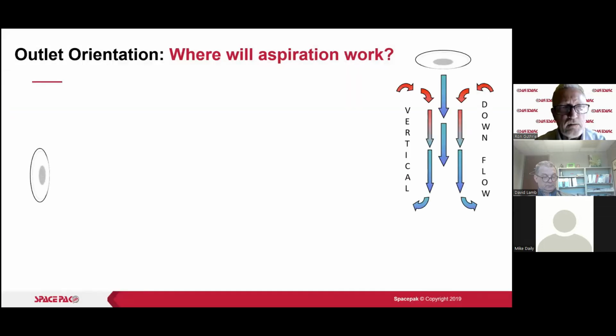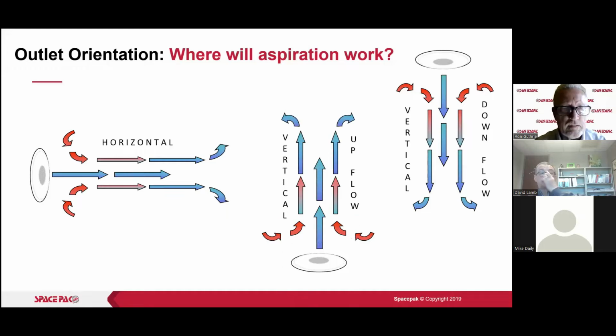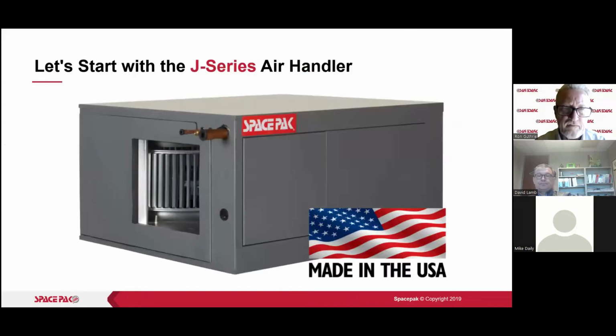Now what that gives us is less than 2-degree temperature differential within the room. So we eliminate most of the stratification in a room. And as I had mentioned before, even on a hot ceiling, we're not convecting heat through the ceiling into the attic and out of the room. So that's an inherent efficiency that we have within our system. We can use these outlets that work the same in any location, whether in the floor, the ceiling, or horizontal. Aspiration still works the same way. That's another advantage that we have.